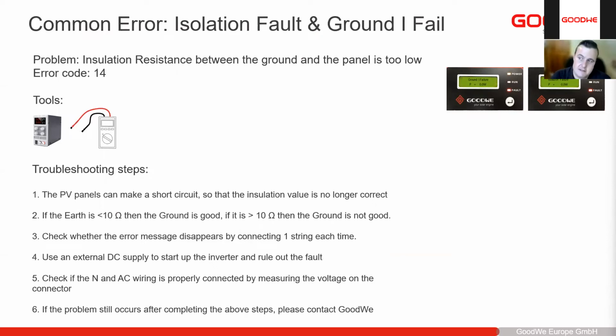In a case like this, the DC power supply does come in handy, because normally an isolation fault or ground I fail is a site-related query. If you power the device on with a DC power supply and you still have that fault, then that could indicate internal components have failed. Very often the PV modules can make a short circuit internally, or the insulation value is no longer correct. So that's why an insulation resistance tester is also good to use in this instance.